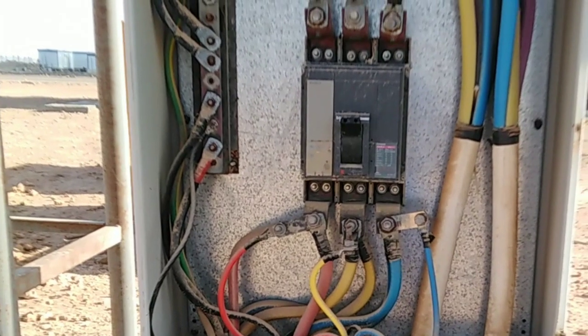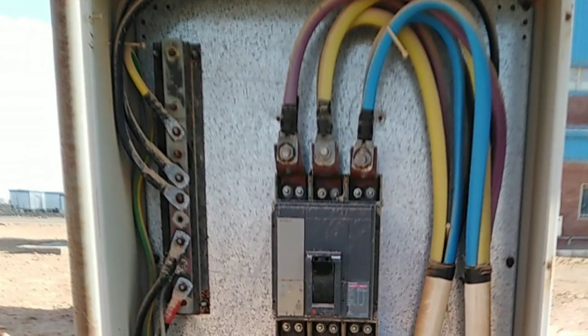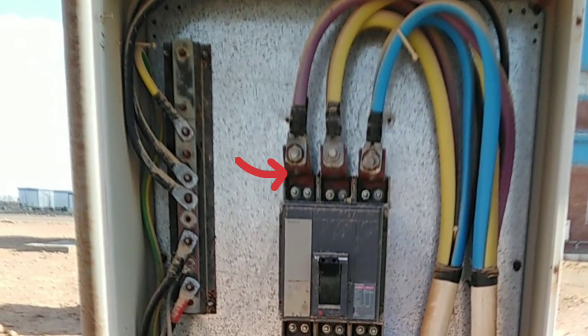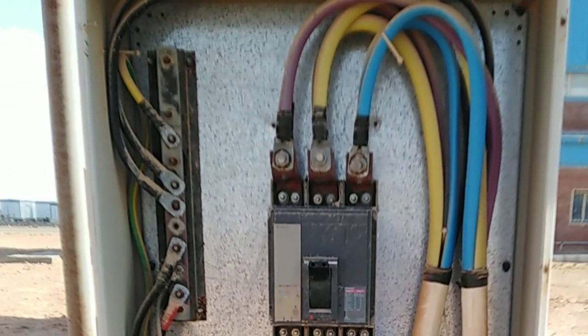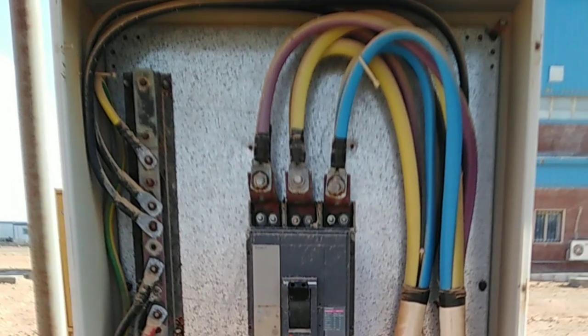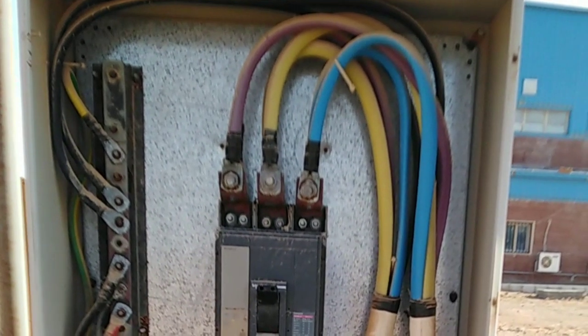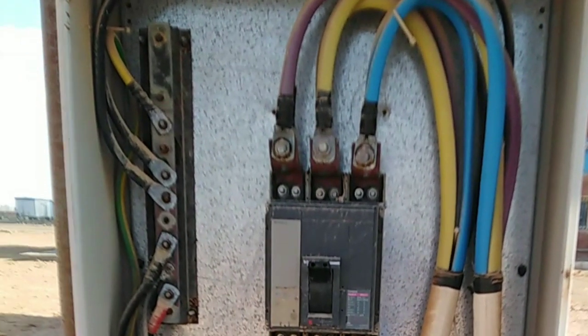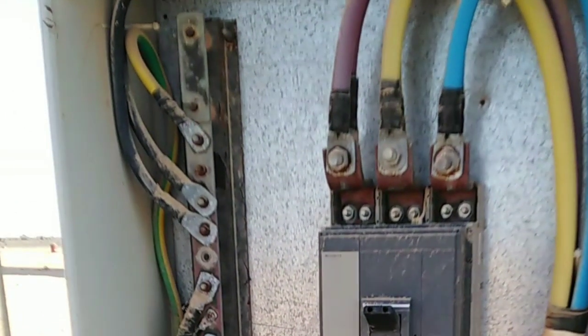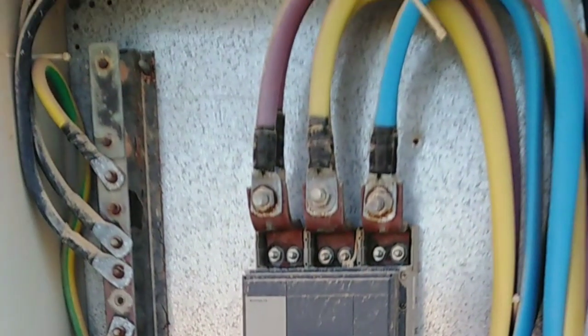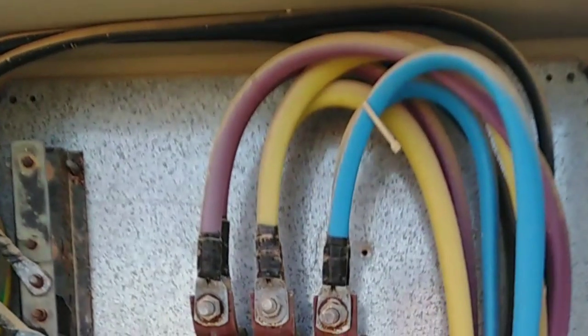Another thing in this panel is the corrosion effect. You can see the corrosion has already started on the cable terminals and bolts. This corrosion can cause the cable terminals to break down and cause a short circuit. A regular inspection can help you find hazards like this one. All electrical panels should have a suitable, secured door. A warning label should be on the door.